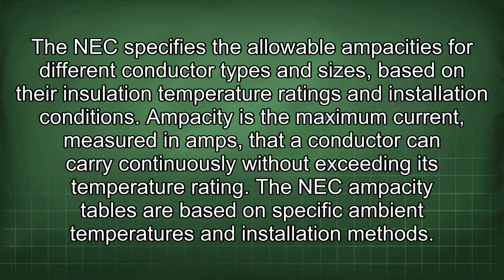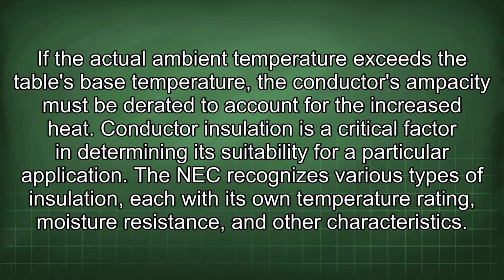The NEC specifies the allowable ampacities for different conductor types and sizes based on their insulation temperature ratings and installation conditions. Ampacity is the maximum current, measured in amps, that a conductor can carry continuously without exceeding its temperature rating. The NEC ampacity tables are based on specific ambient temperatures and installation methods. If the actual ambient temperature exceeds the table's base temperature, the conductor's ampacity must be derated to account for the increased heat. Conductor insulation is a critical factor in determining its suitability for a particular application.